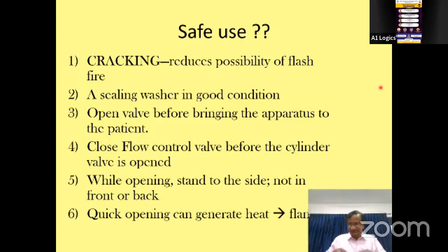As soon as you take a cylinder, a new one comes in and we attach it to the pipeline. What you do is open it and close it quickly — this is called cracking. Sometimes there may be small dirt in the outlet port, and if you fix it directly to the pipeline and open it, the dirt may travel and block the pipeline side. So to prevent that, we do this opening and closing, which is called cracking.